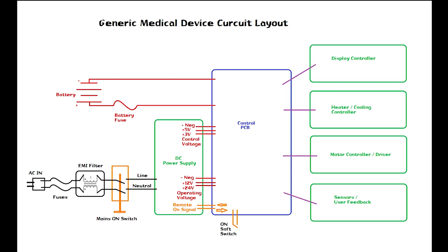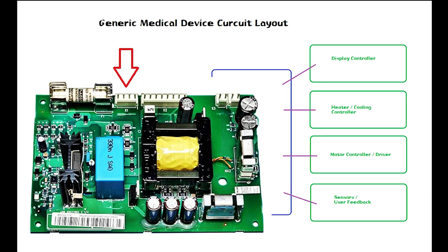Okay, now you check to make sure that your power cord is not bad, make sure it's plugged in correctly. And from there you can go immediately inside the device and you start checking for your EMI filter, because your EMI filter usually has really good access points that come out of it.